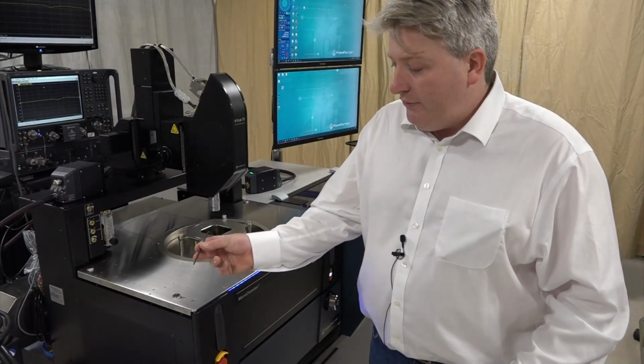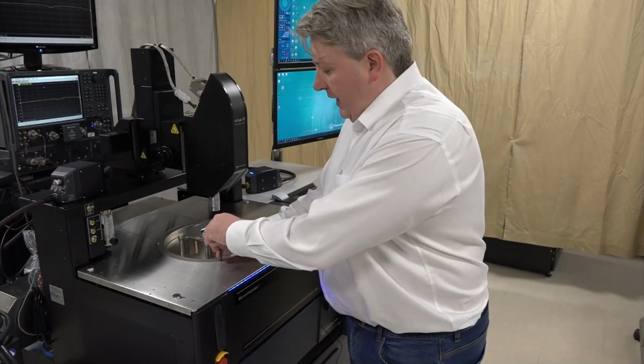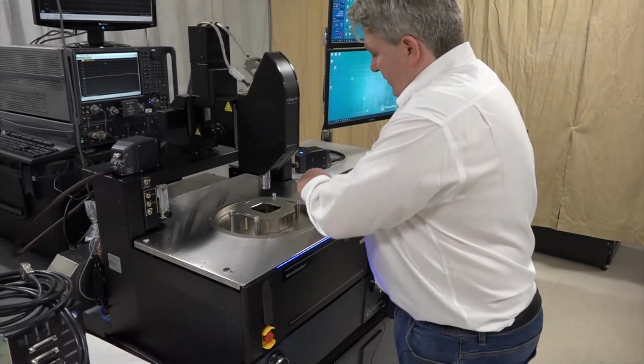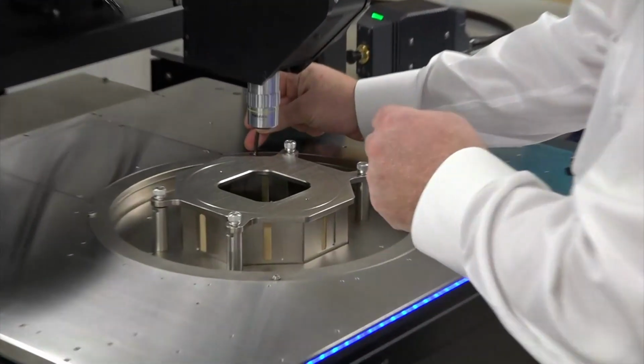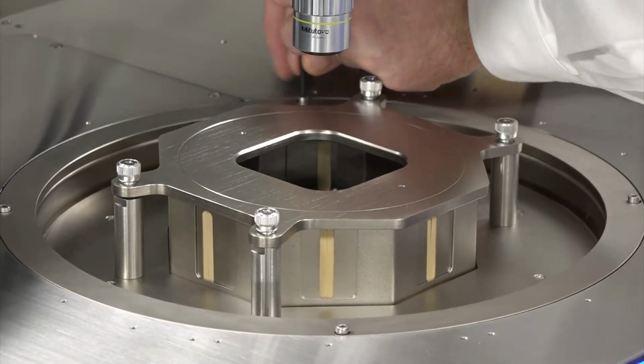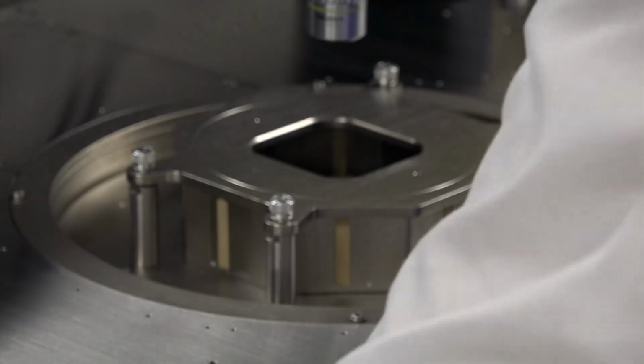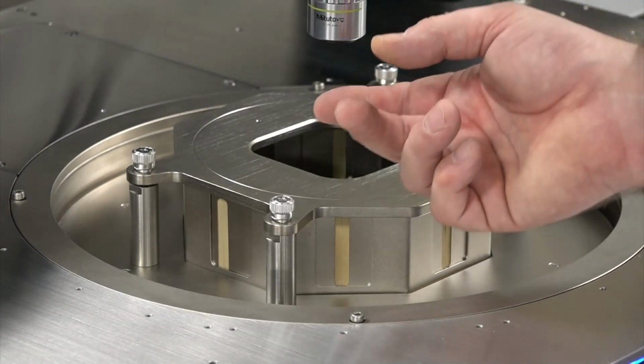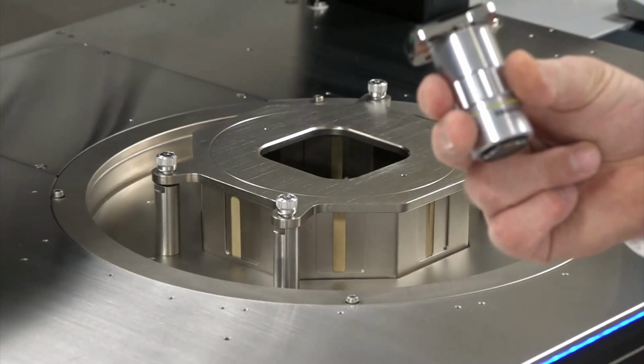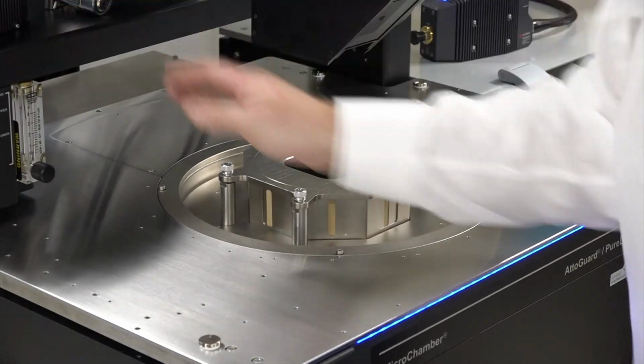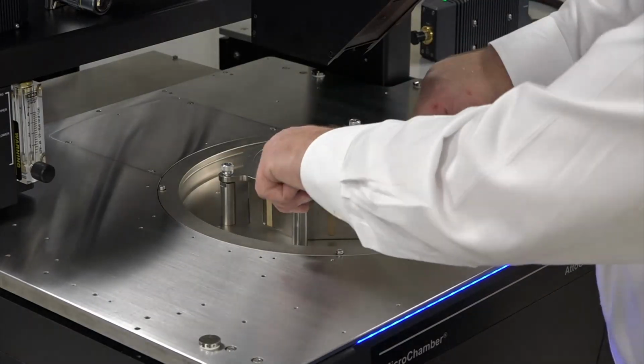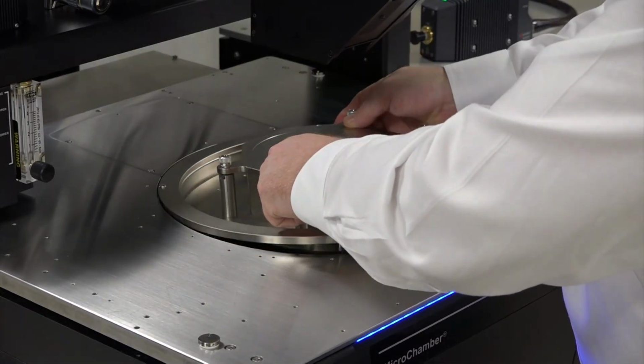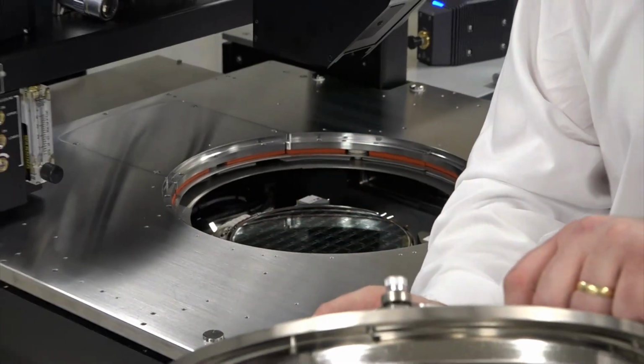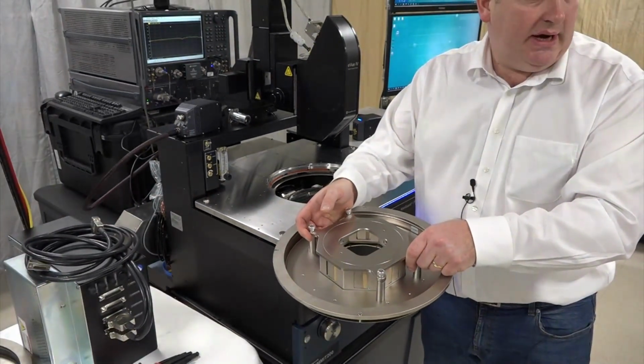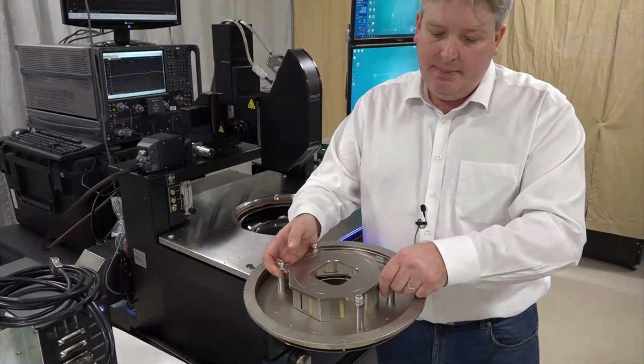We just take a 3mm Allen wrench, undo the 4 M4 screws, these ones. I remove those screws, and if I want to get a bit more space, I can remove the objective from the machine like that. Make sure that I don't catch it on the way out. Make sure these are in. And I can lift this like so, just straight out of the machine. And I find somewhere nice and soft to put it down on, so it's not damaged.